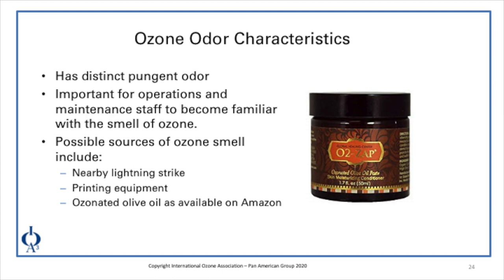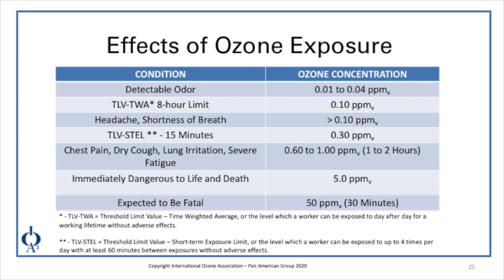Ozone does have a pungent odor, and it is important for operations and maintenance staff to become familiar with the smell of ozone. Some possible sources of ozone smell that you may be familiar with include lightning strikes and the process of printing equipment, which also gives off an ozone smell. Ozonated olive oils, which you can purchase online, actually hold the ozone smell and can be used to get an idea of what that smell is. The detectable odor level at which most people can detect the presence of ozone is 0.01 to 0.04 parts per million by volume.